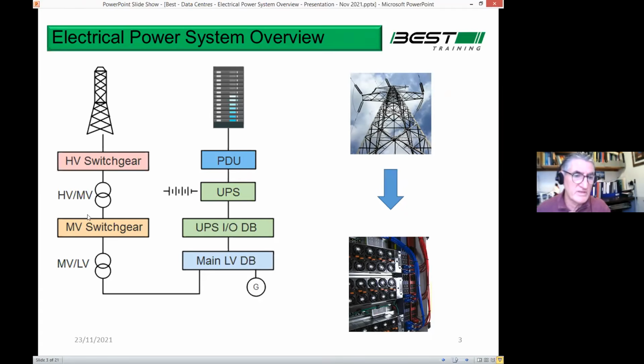So this is what we're looking at today, with the main focus here from the medium voltage switchgear down. And the right-hand graphic is just showing it there. Look, big transmission pylon in there, whatever that would be, at 220 kV or 110 kV. And the power is going right back into the back of the rack. This is the servers, the back of the server rack. And you can see the power coming in here. The red and blue leads are the cables going up onto the actual servers. And so we're going to talk you through all of that.